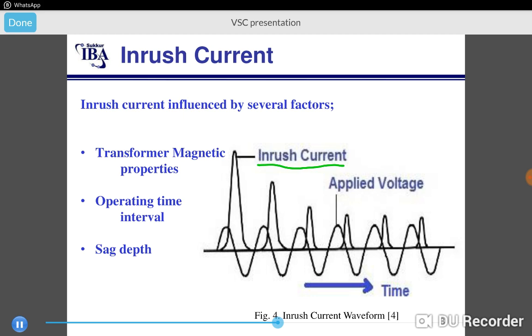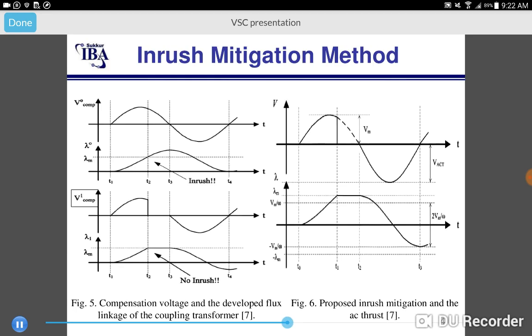This inrush current damages transformer insulation. Even sometimes it stimulates over current protection, and eventually fails the compensation. Due to this reason, many researchers are working to reduce or mitigate this inrush current. The common approach used by most of the researchers is controlling the inrush current by applying PWM techniques on the compensated voltage.